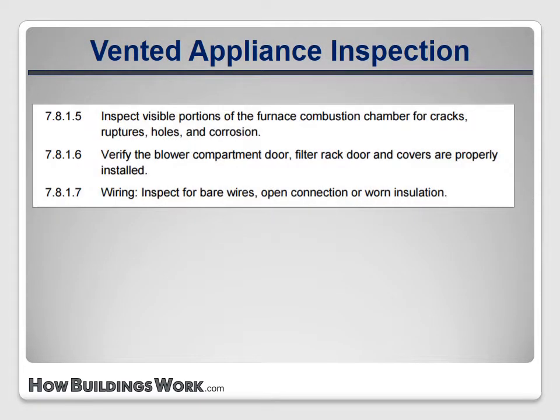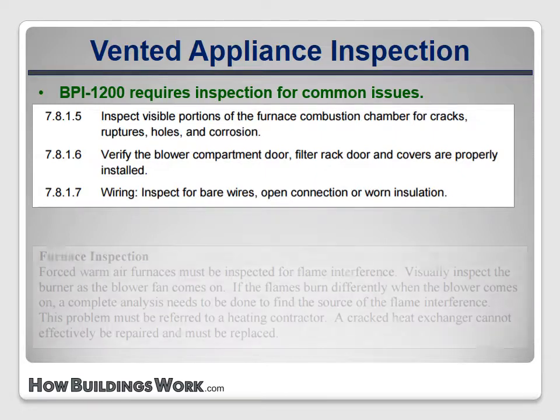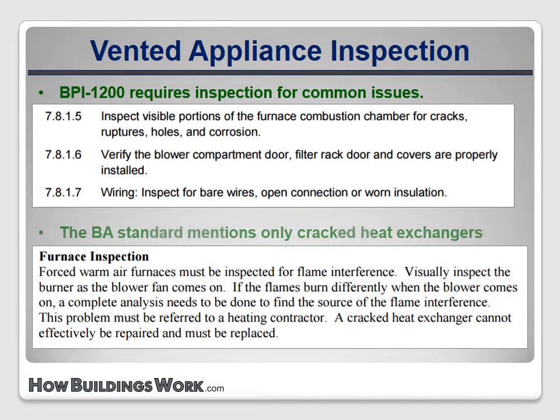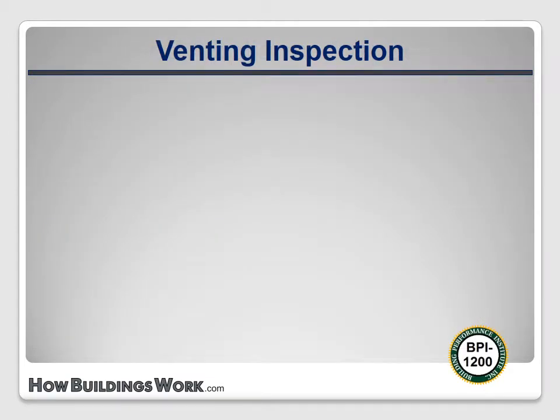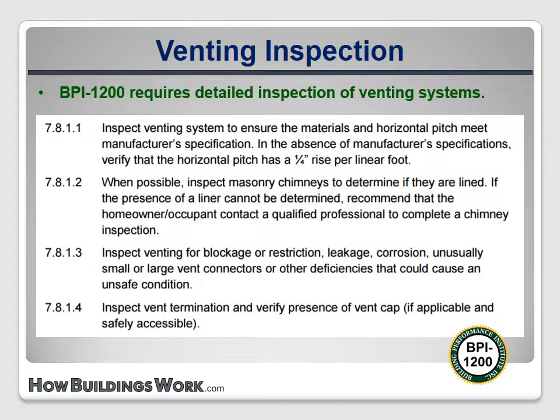BPI 1200 requires that a number of details be inspected on vented appliances, including wiring and integrity of ducted system components. The only one of these noted in the BA Standard is the furnace heat exchanger inspection. BPI 1200 also requires detailed inspection of venting systems, including vent pitch, proper support and terminations, presence of liners, and assessment of condition for rust and deterioration. None of this information is detailed in the BA Standard, but it could serve as a useful list for creating an inspection checklist.